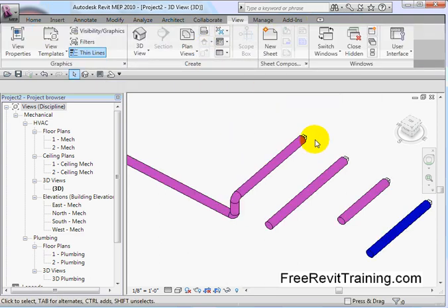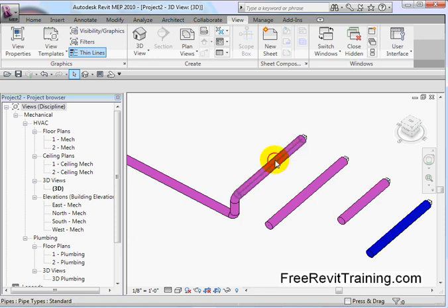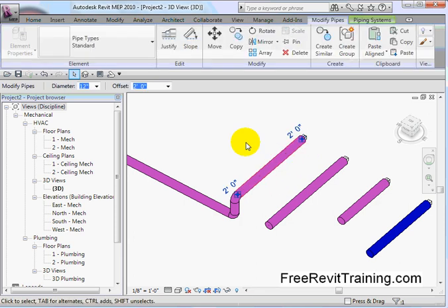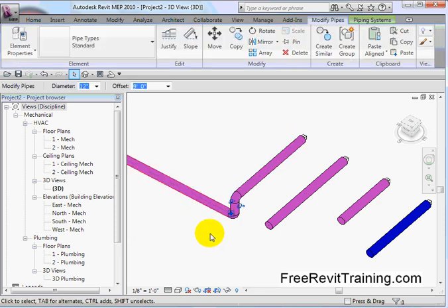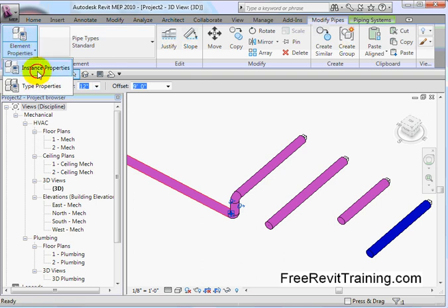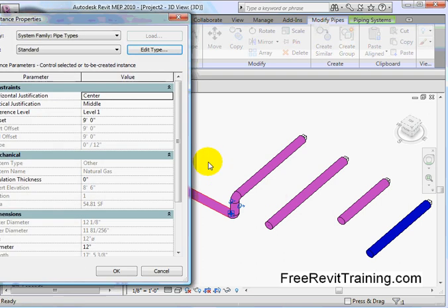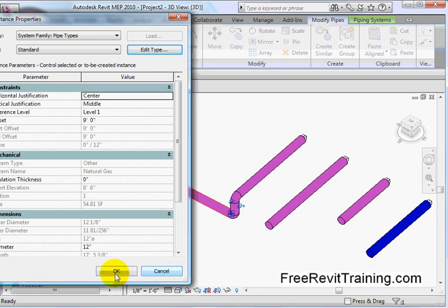So what I'm going to do is I'm going to grab this pipe set here, and it's just been added to the system. Now, let's hit finish system. And what we've done is, within this other, now I'm going to click on it again. You'll see it's a piece of pipe. Let's click one down here just to verify. I click that piece of pipe, and I go to elements. I go to instance properties, and if all goes well, you'll see it says system type other natural gas. Pretty sweet.